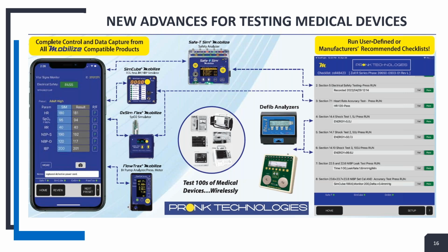And then it's alarmed to what, 30, I think it is. It wants you to set the ECG to 30. Right now we're set for 120. So if you hit run, there should be a run button on the right there. It should change the heart rate to 30. And I don't remember if we programmed the alarms or not.